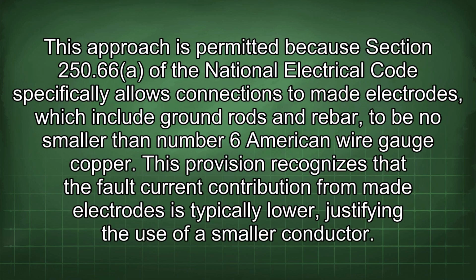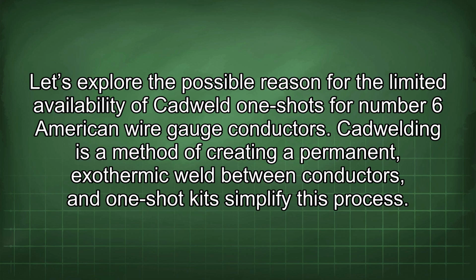This approach is permitted because section 250.66 of the National Electrical Code specifically allows connections to made electrodes, which include ground rods and rebar, to be no smaller than number 6 American wire gauge copper. This provision recognizes that the fault current contribution for made electrodes is typically lower, justifying the use of a smaller conductor. Let's explore the possible reason for the limited availability of Cadweld one shots for number 6 American wire gauge conductors.